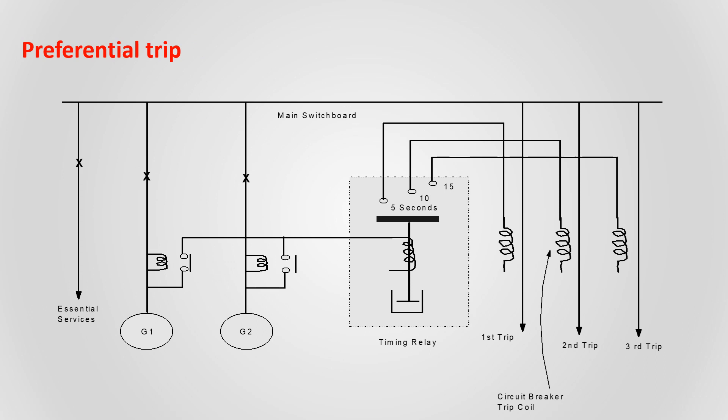Preferential trip can be tested either by primary current injection method or secondary current injection method. This trip arrangement is for an overload of generator, so we are applying a current injection method for testing this preferential trip.